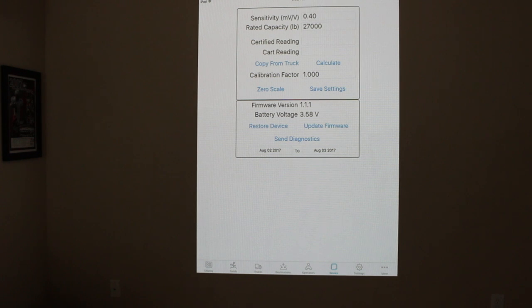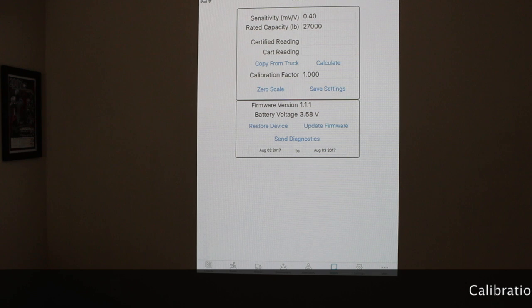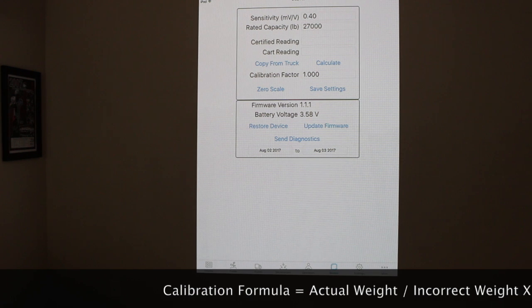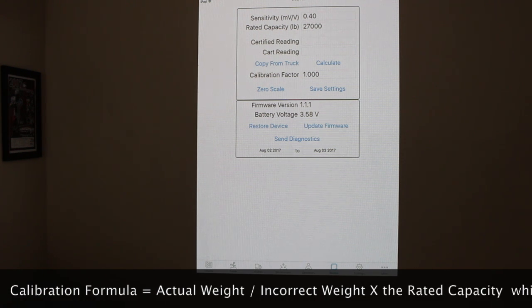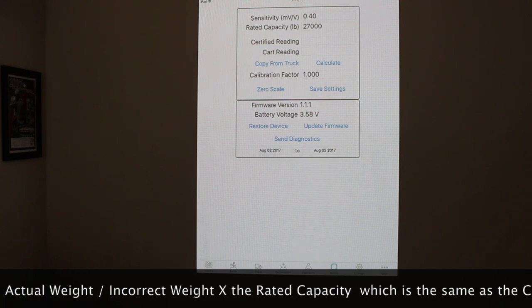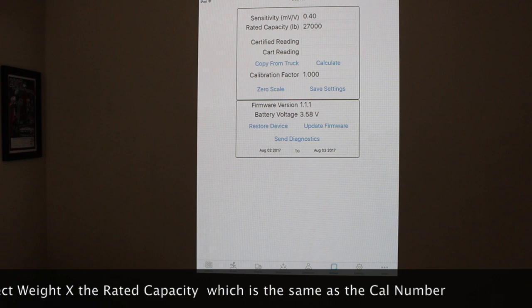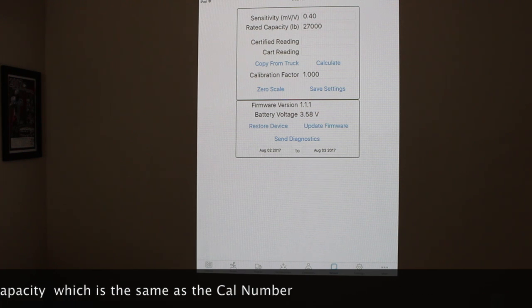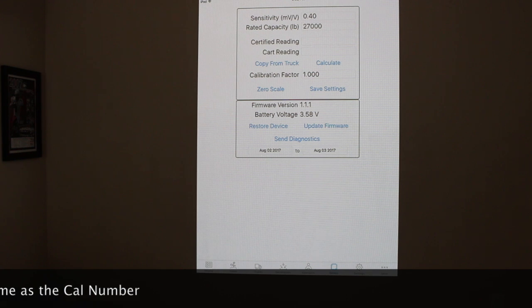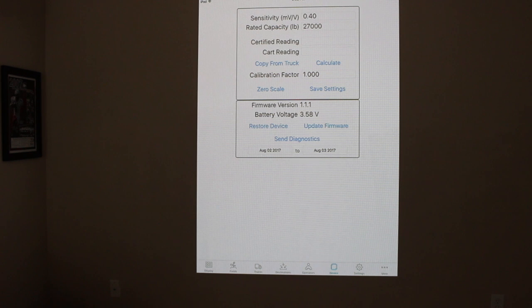The calibration formula is very simple. It's just basically going off of a percentage of error. So the calibration formula is this. Take the actual weight of what the certified scale tells you, divide that by what the incorrect weight or what the cart weight is telling you. It will give you your percentage of error. So if I'm at 1.01, I would take that times that 27,000 and I would get 27,270 would be my new number.